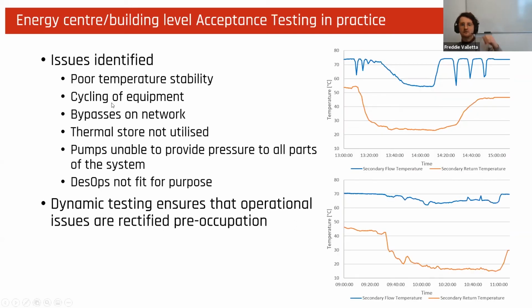In practice, these are some of the issues that we've observed on site. As you can see, there's a whole range of issues from heat generation equipment to pumps and the network commissioning, and also the controls as a whole. With an example on the right-hand side here, these are two iterative tests over 2 days. And these are secondary flow temperature and return temperature on the secondary side of a district heating plate heat exchanger.